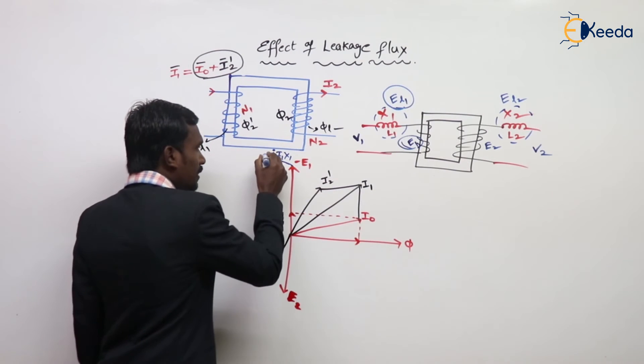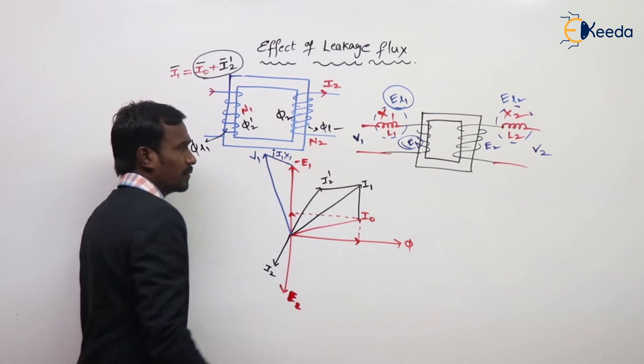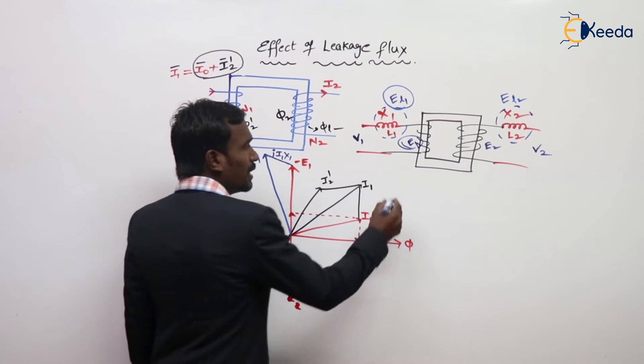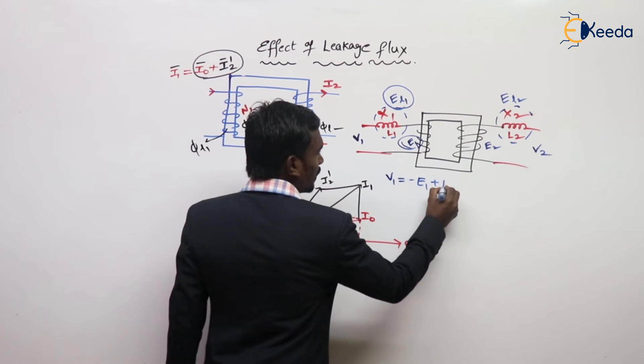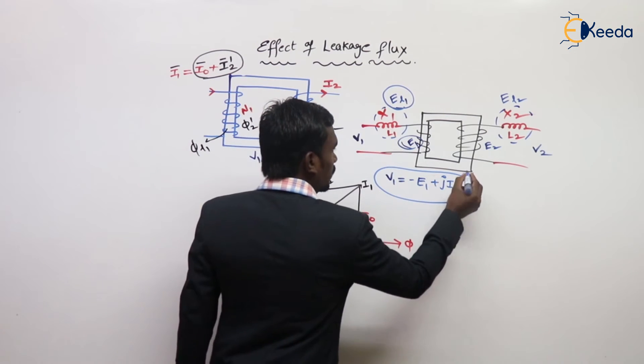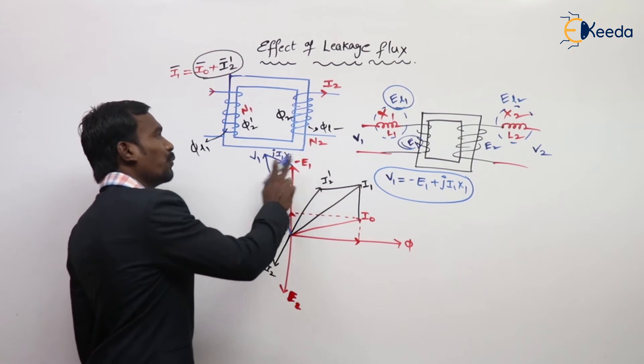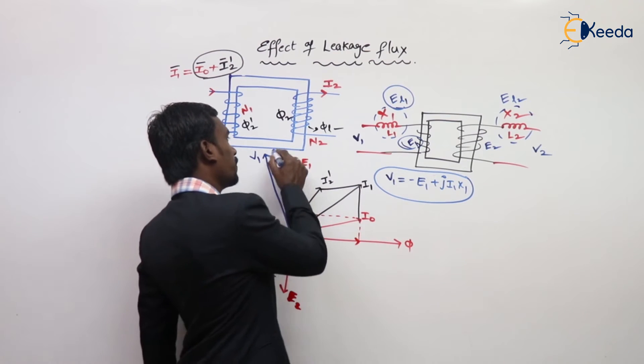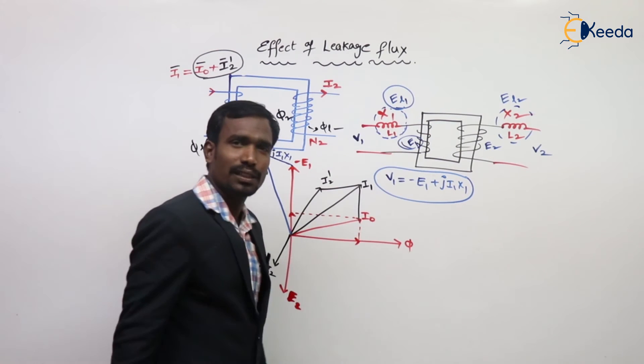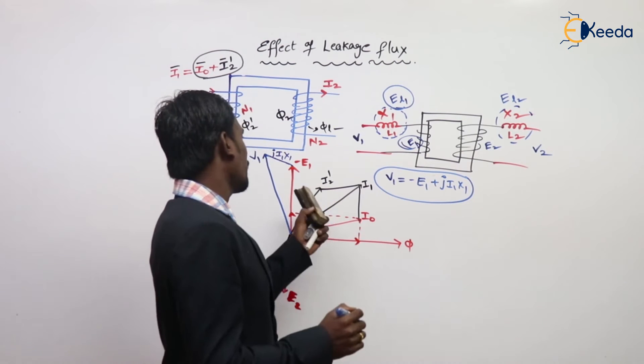So the equation is: E1 + j·I1·X1 = V1, which gives V1 = −E1 + j·I1·X1. This j·I1·X1 term represents the fictitious reactance drop, which compensates the leakage flux voltage in the primary.